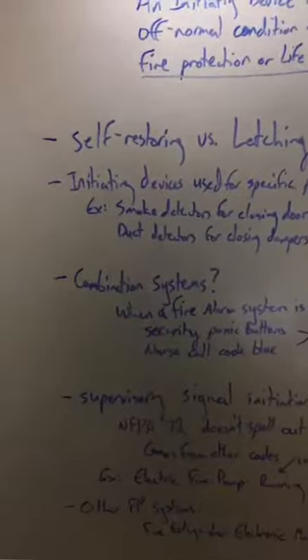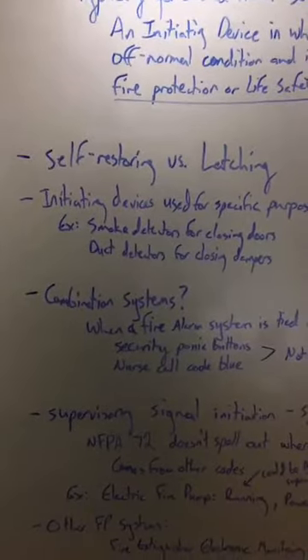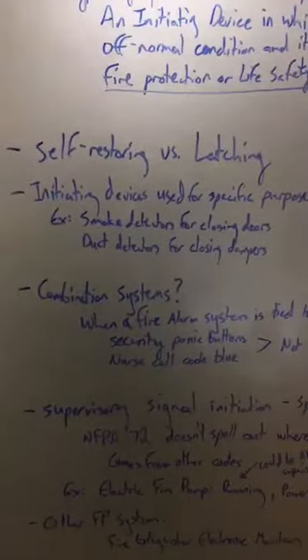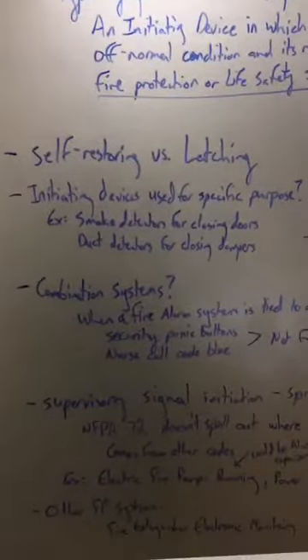Self-restoring versus latching. This is just an indication that some of those supervisory signal initiating devices can either be self-restoring, like an air pressure switch where when it hits a certain low pressure it triggers a supervisory signal, and when that pressure is restored that signal goes away. You also have latching, which requires manual reset.